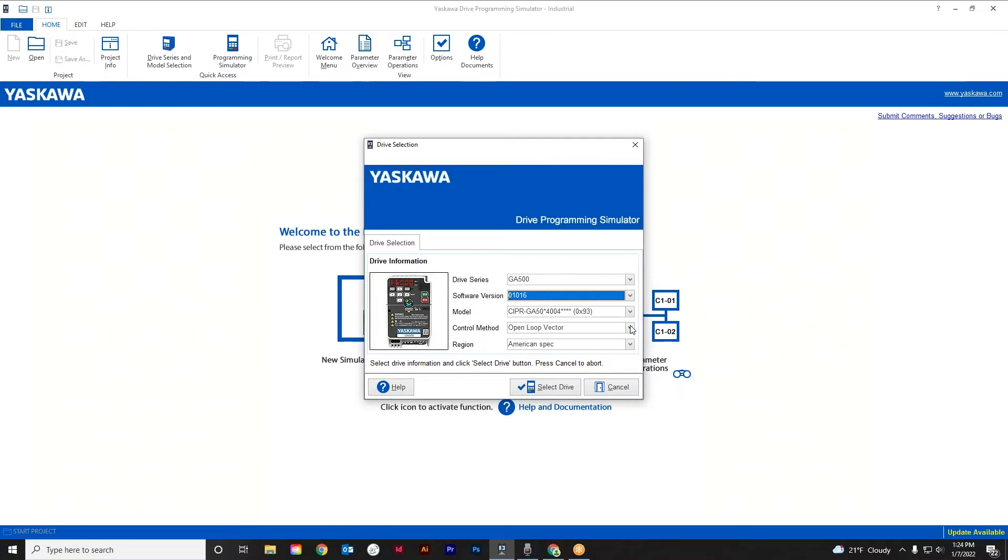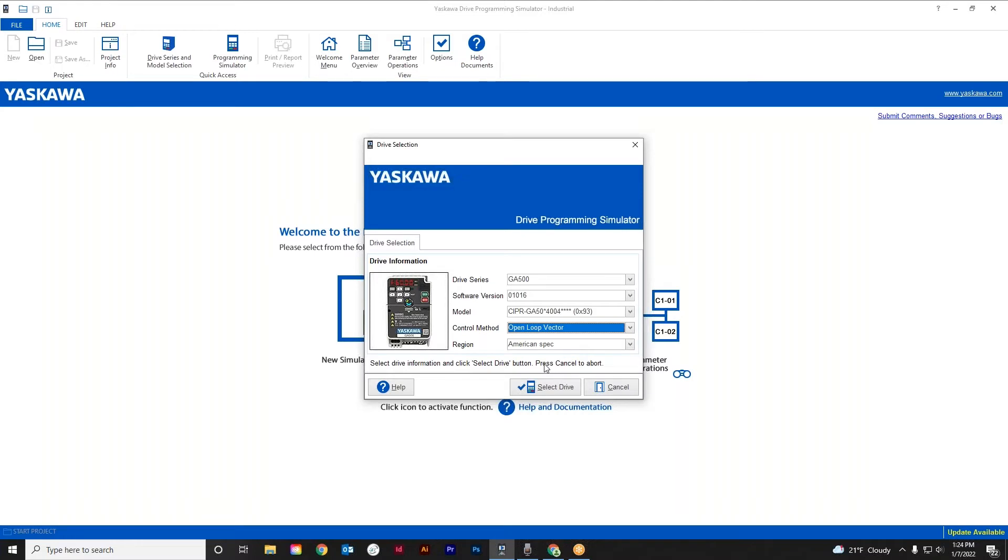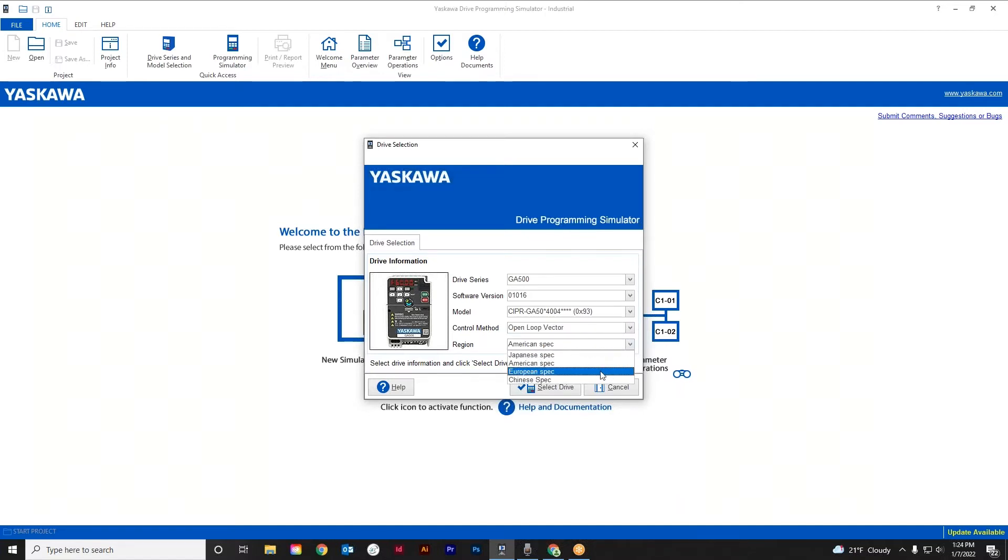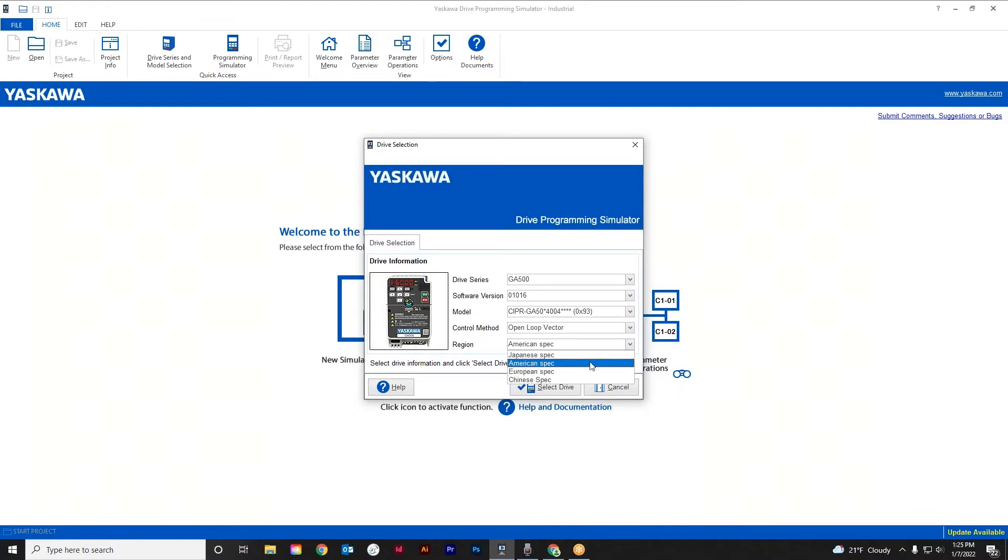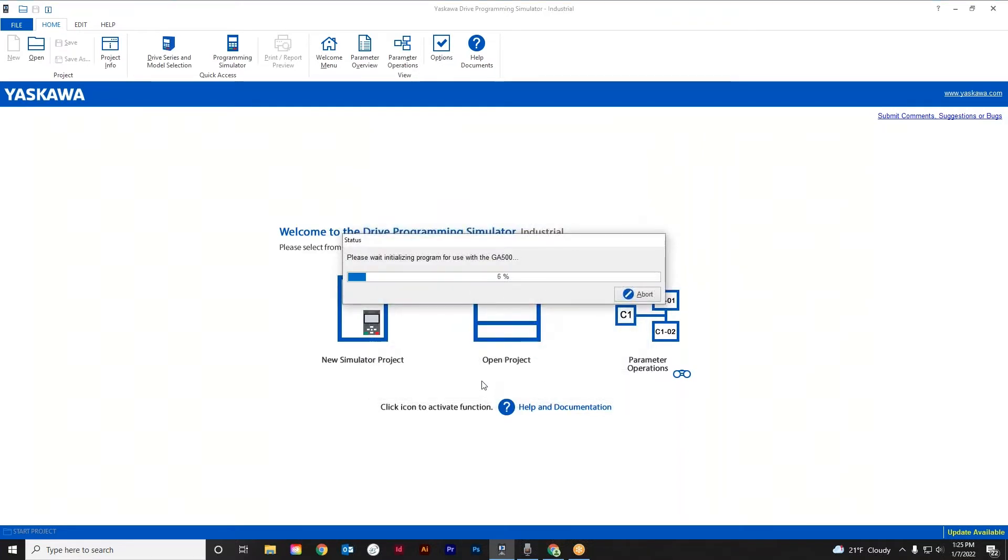Out of the box, these drives are open loop vector. We can make them a few different choices, volts per hertz and a few other ones here, but open loop vector is out of the box, so we'll leave that alone. Something else here for a drop down is region. Default, of course, is the American spec. You know, if you're a world traveler, you can pick the Japanese or European, but obviously here in the States we want the American spec. So at this point we're going to hit select drive, and it'll get all the parameters loaded for that particular horsepower.